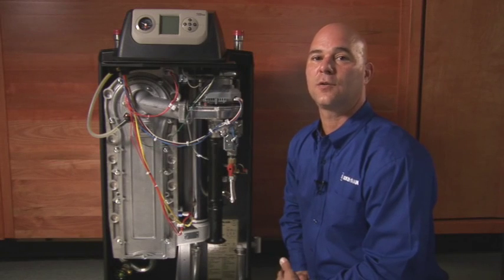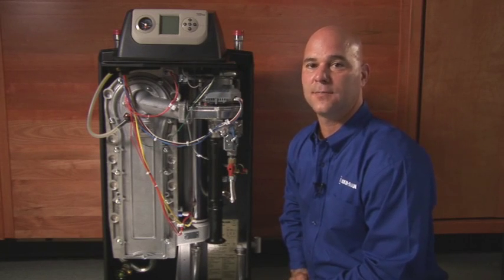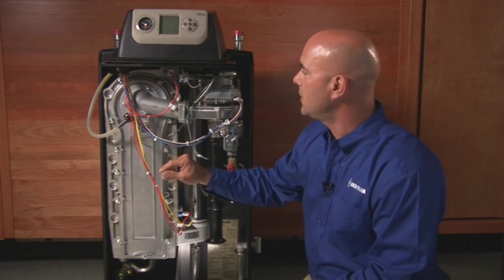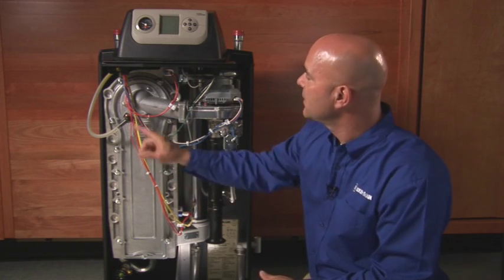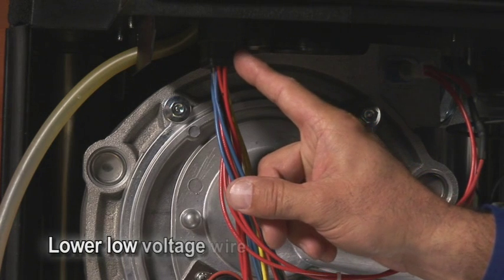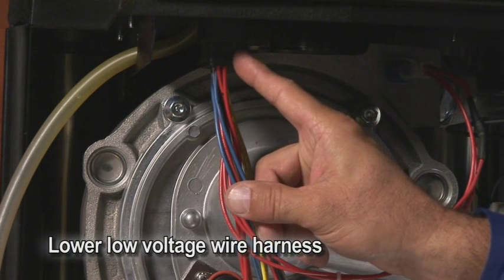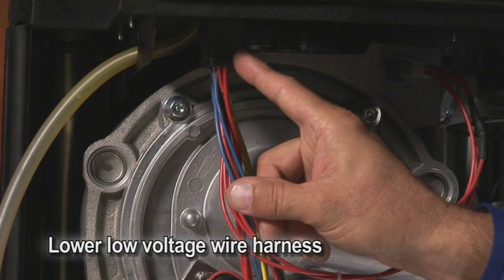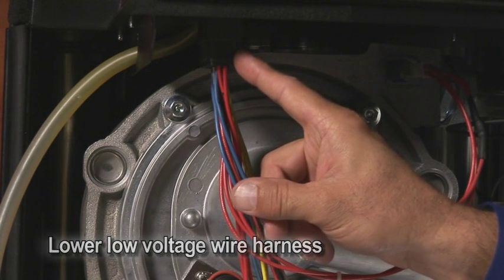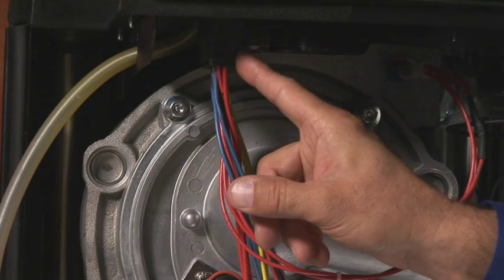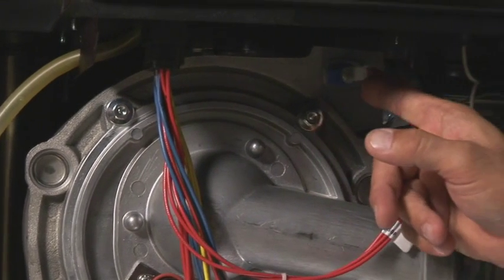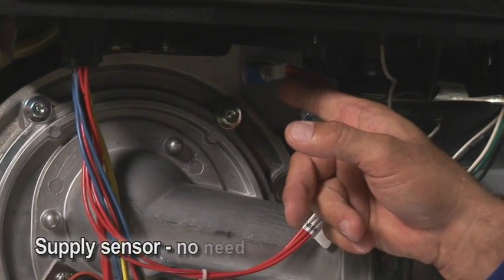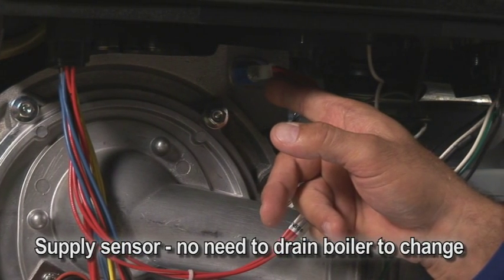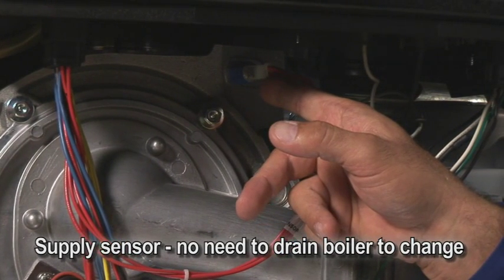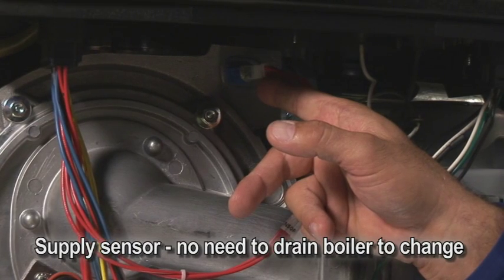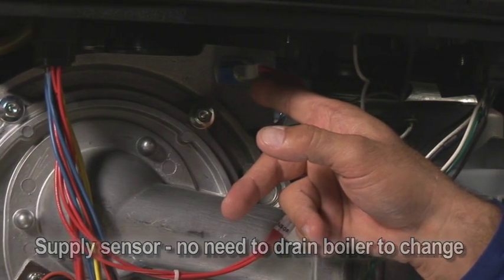In this segment, we're going to go through the ultra boiler components. In the heat exchanger compartment, we have a lot of components here. First, we have a 16-pin connector. This transfers the wiring from the U-control down into the heat exchanger compartment. Out of this 16-pin connector, we come across and we put a signal cable to the supply sensor on the block. This is called a block sensor. It's a dry sensor. You do not have to drain the boiler if you need to change the sensor out.